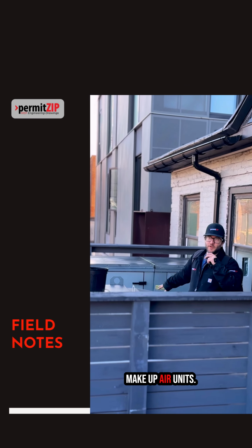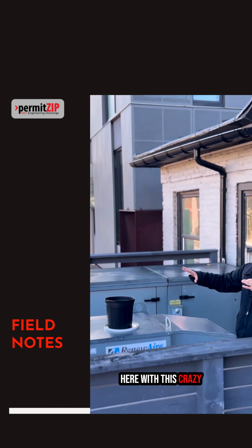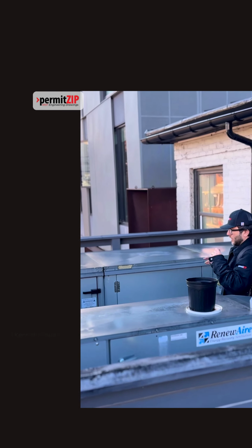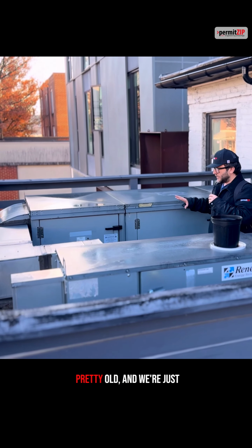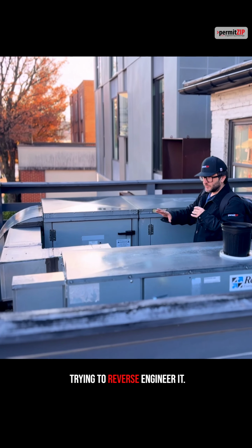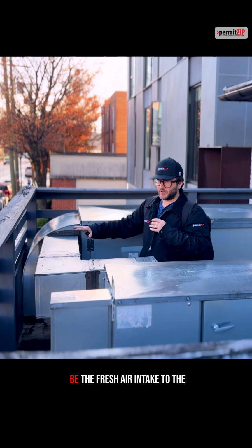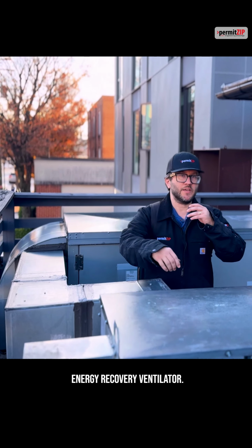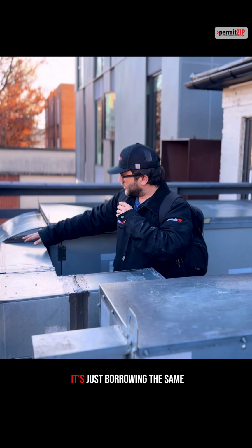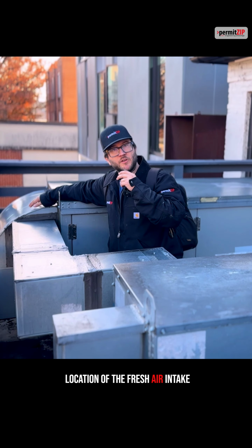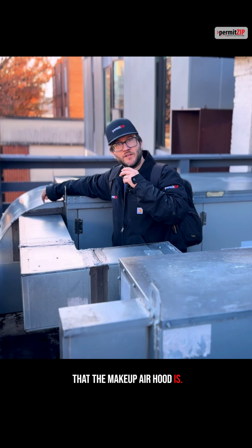ERVs, makeup air units, what's going on here with this crazy mechanical system? It looks pretty legacy, pretty old, and we're just trying to reverse engineer it. This appears to be the fresh air intake to the energy recovery ventilator. It's just borrowing the same location of the fresh air intake that the makeup air hood is.